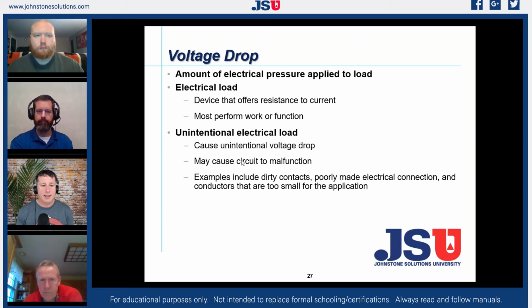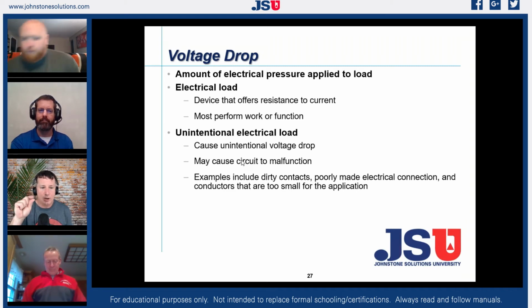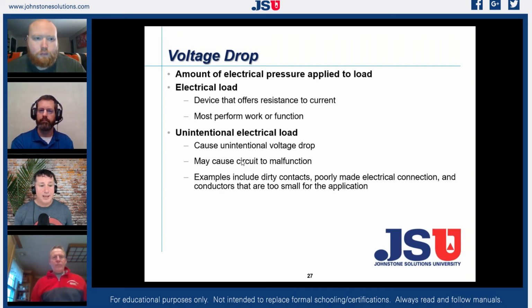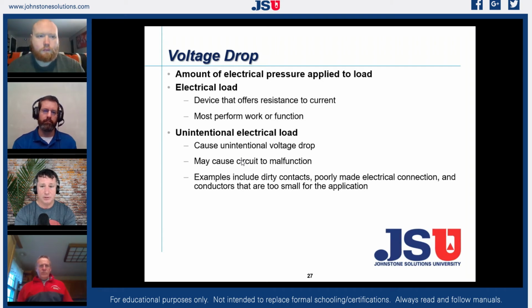Absolutely. And part of that class, and I encourage you guys to go back and look at our relays and contactors class that we have on the Johnstone Solutions University on YouTube, because we actually burn out contact points on a contactor. A contactor was only good one time, the very first time it was energized. We arc across those contact points every single time it opens and closes. So we change the molecular surface of our contact points continually. And as we reduce the surface contact, we lose the ability to move our current through there properly, because those contact points were designed for a load to pass through, not to stop.